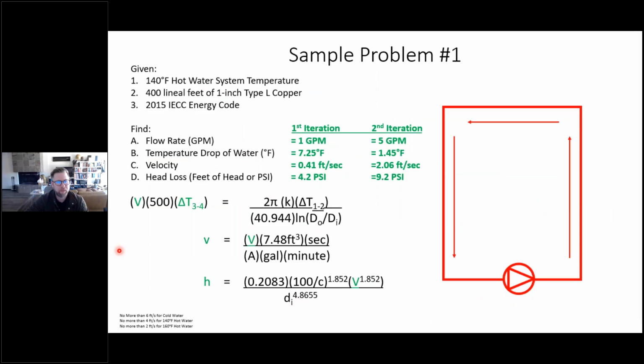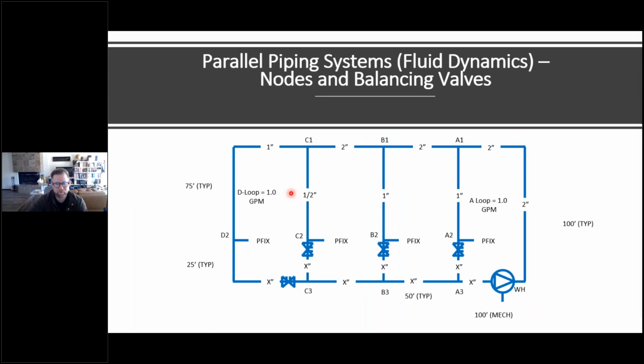If we assumed a 1 GPM flow rate going through, we would end up with a 7.25 degree Fahrenheit temperature loss, a 0.41 foot per second maximum velocity, and 4.2 psi. And that was based off of the calculations. Now, if we bumped up that assumed flow rate, like Hardy Cross says, to 5 GPM, we would see the second go around as we answered these questions, the temperature drop would be 1.45 degrees Fahrenheit. So again, we increase flow rate, the temperature drop goes down. Our velocity increases for the second go around because our flow rate increases while we kept the pipe constant. And the head loss would increase because the velocity increases, and based on our Hazen-Williams equation, we would see that increase to 9.2 psi.